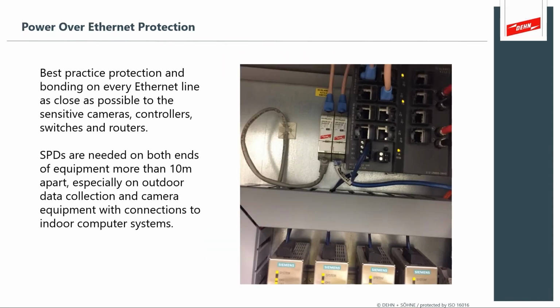Power over Ethernet. We're seeing more and more types of highly exposed devices, routers, sensitive cameras, switches, and controllers that are spread around the power plant. And what we see is that these power over Ethernet devices need to be protected at both ends. Again, out at the security cameras or the power over Ethernet appliance, and then back inside the cabinet at the switch and the routers to protect both ends.